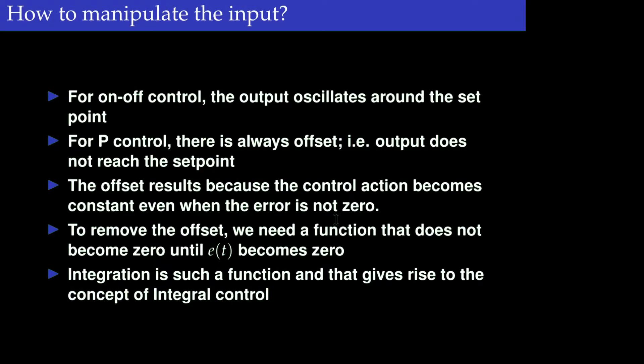We have seen on-off control and P control. For on-off control, the output oscillates around the set point and the output is never steady at the desired value. For P control, the main problem is with the offset, meaning that the output really does not reach the set point value. The offset results because the control action becomes constant even when the error is not zero.